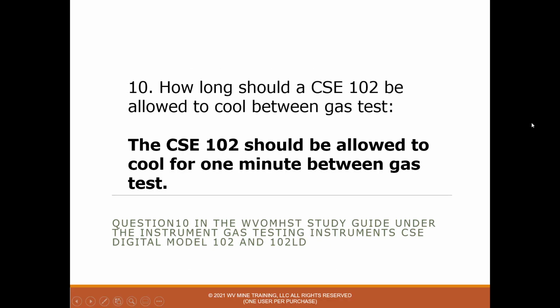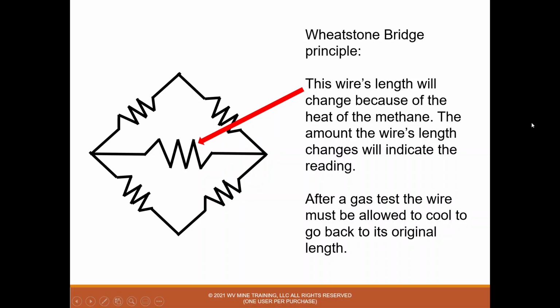Question 10, how long should a CSE 102 be allowed to cool between gas tests? And the answer is the CSE 102 should be allowed to cool for 1 minute between gas tests. So here's a little picture of this. All these detectors work on a Wheatstone bridge principle. So I have a little arrow here.